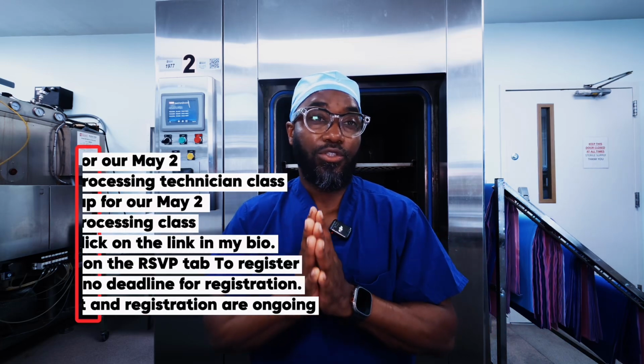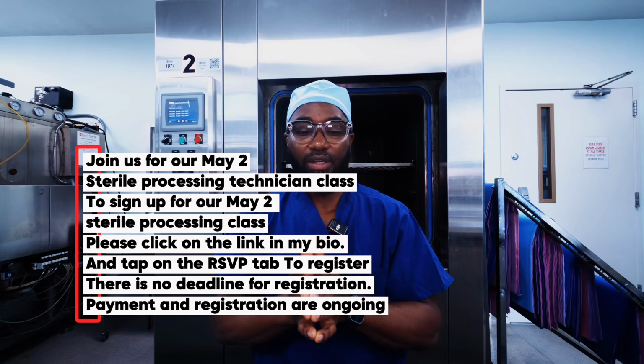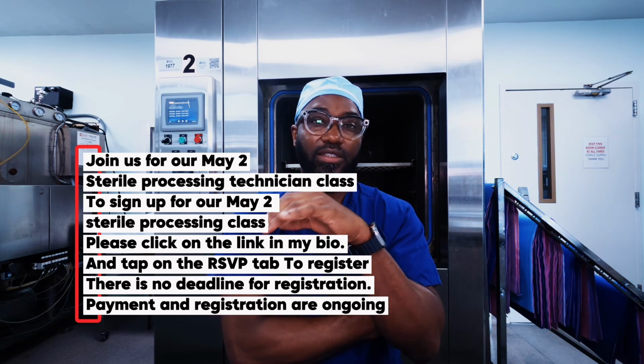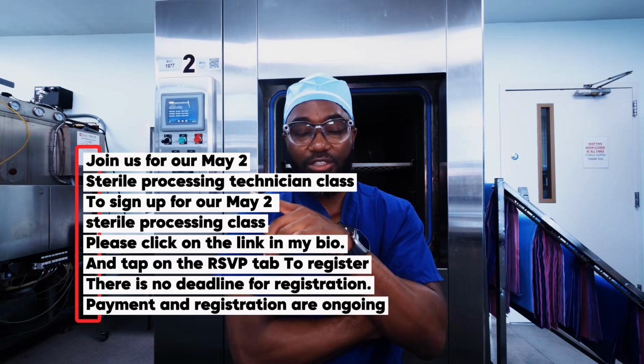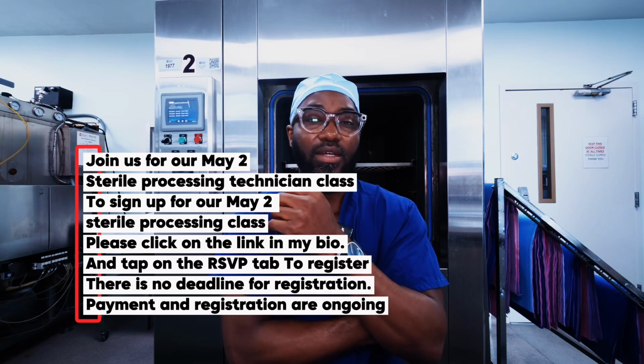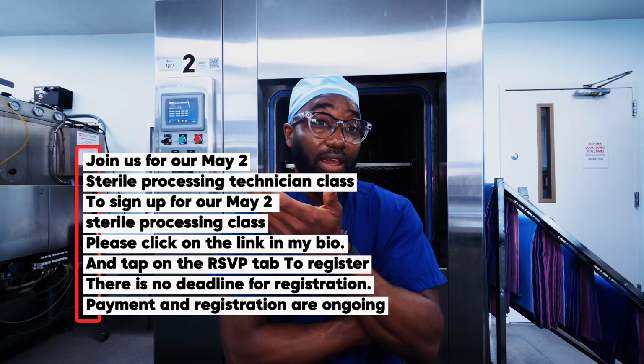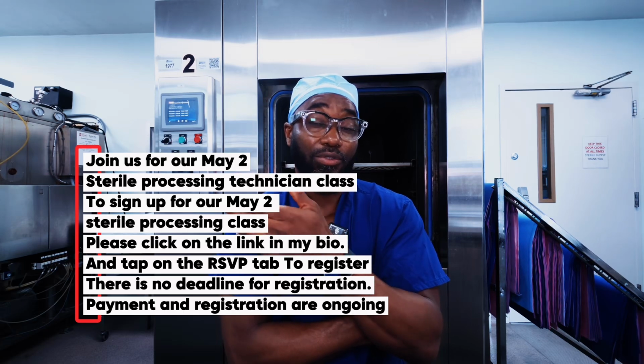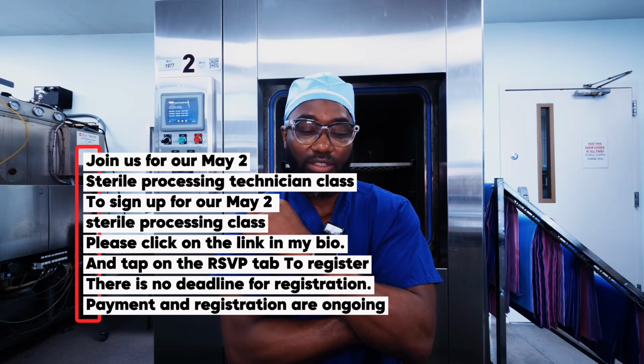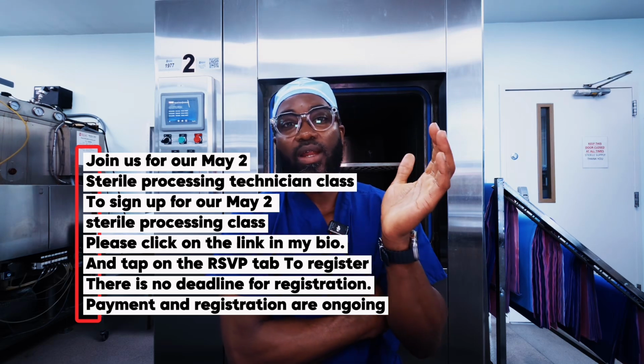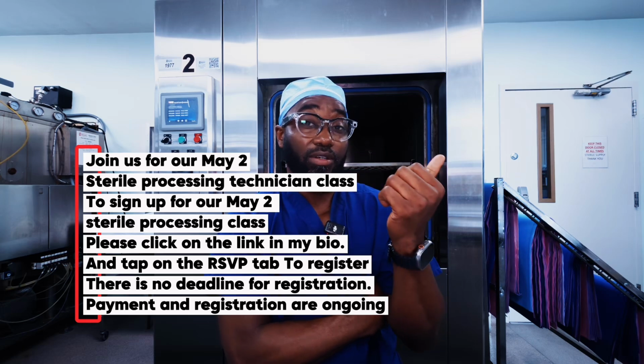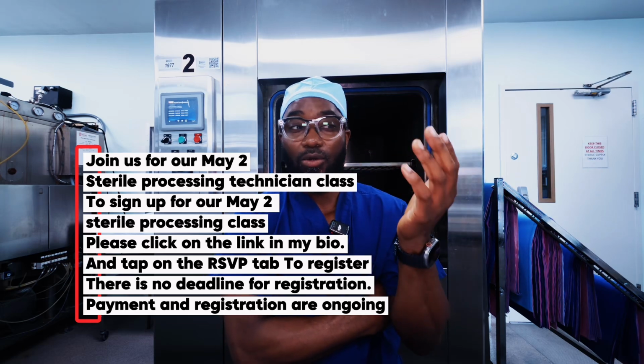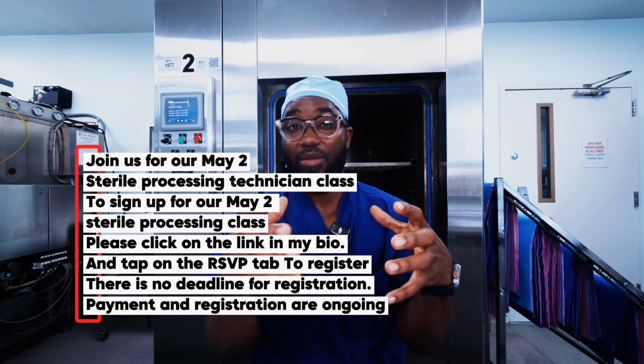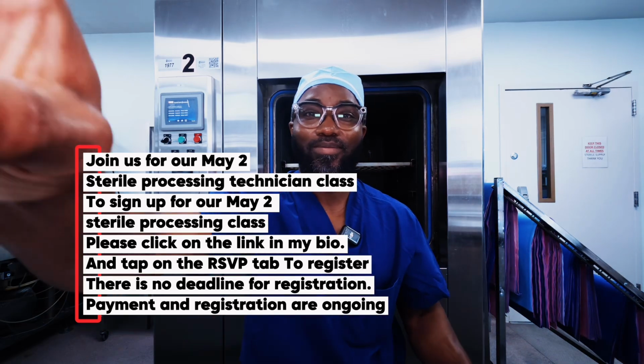But in order to run a good sterilization cycle, it has to have those three qualification tests, which are your chemical, biological, and physical printout tests, that will verify and assure you that your instruments were sterile during the sterilization process. So that's what happens in order to sterilize a load. There's a lot that goes on behind the scenes before this tray makes it out to the operating room. Hope that helps.